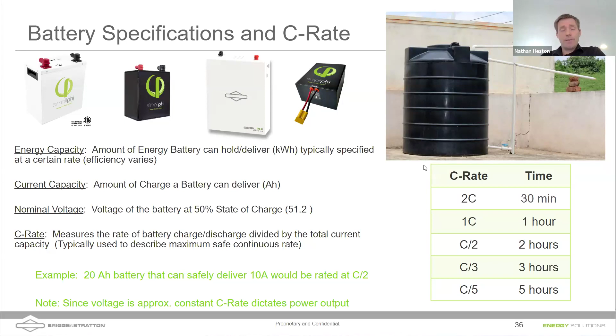It's important, as you're designing your system, to design it with the appropriate size, scale, and voltage in mind. If you go to lower voltage batteries, and we do make 24 volt PHI batteries, that means your cabling has to be that much bigger. If you halve the voltage, you have to double the current. So do think about that as you're designing systems.